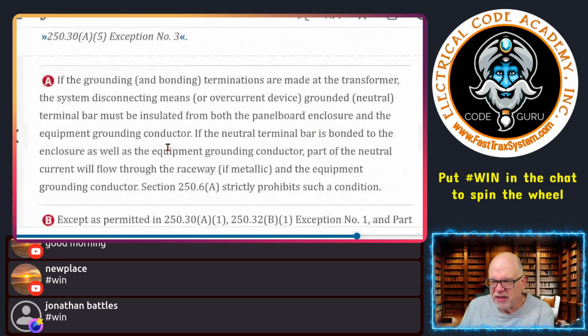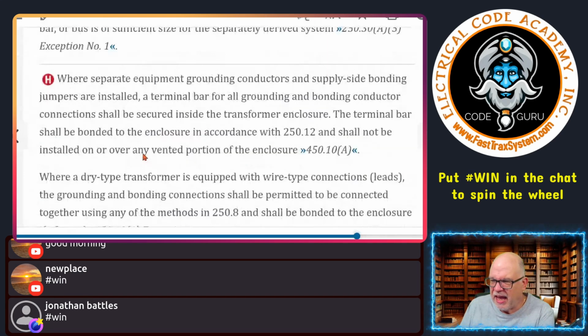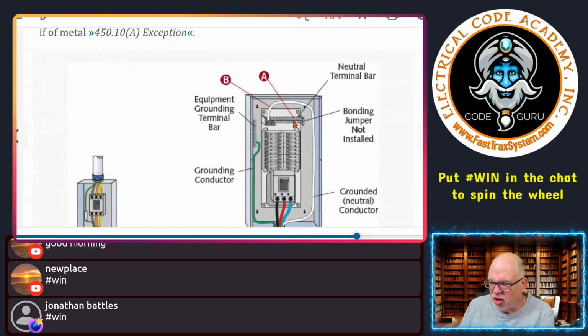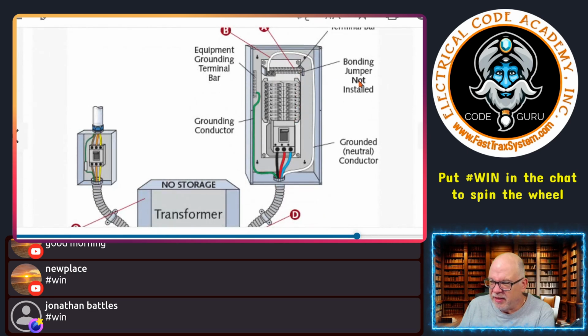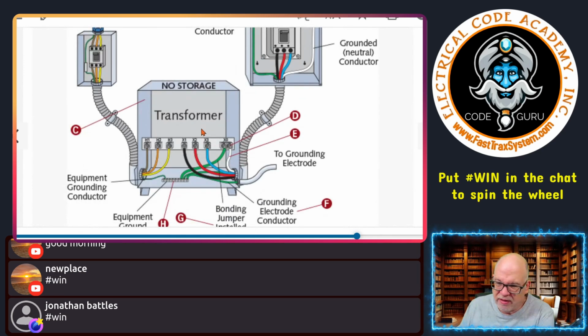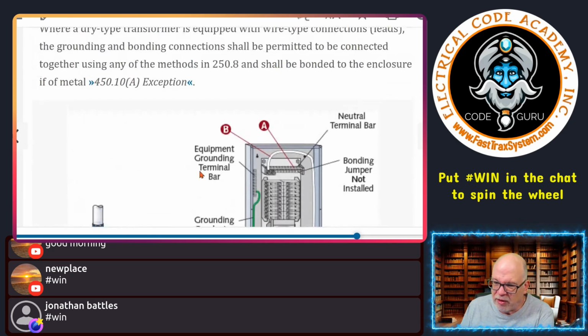So let's see here. For A, it's calling out right here. Right? And you notice something right here, okay? The system bonding jumper is not installed. It's being chosen to be installed here, right? And it's going to be sized based on these derived conductors right here, by the way, in case you didn't know, right? And ultimately, the system bonding jumper 250.28 A, B, C, and D is going to ultimately send you to sizing 250.102C, okay? But this is sized right here. And this is the system bonding jumper right here. So we do it here, right? And we're not doing it here.